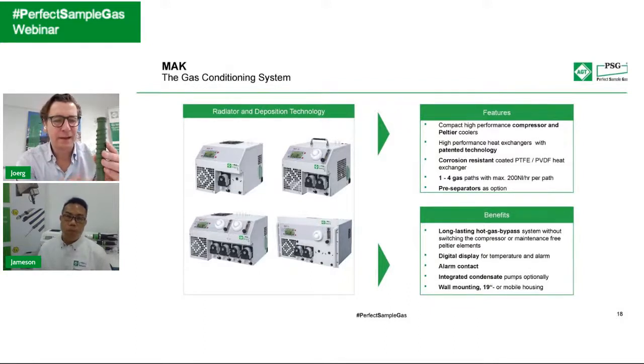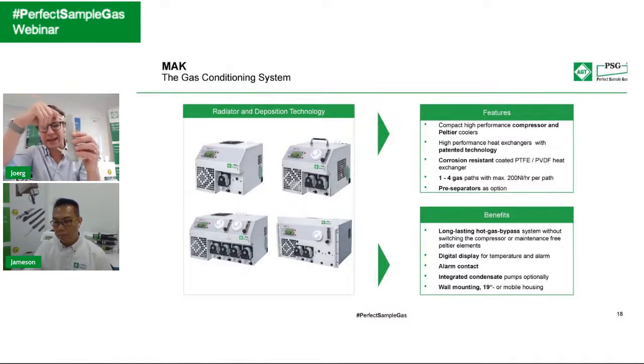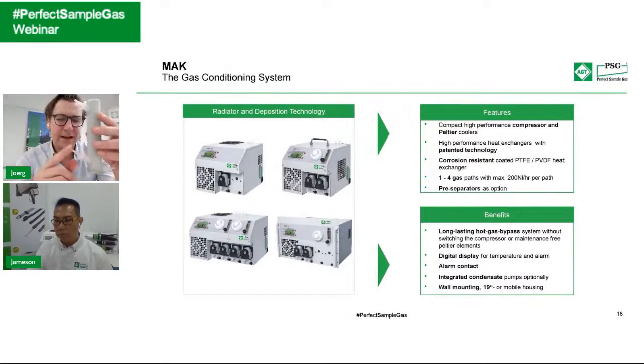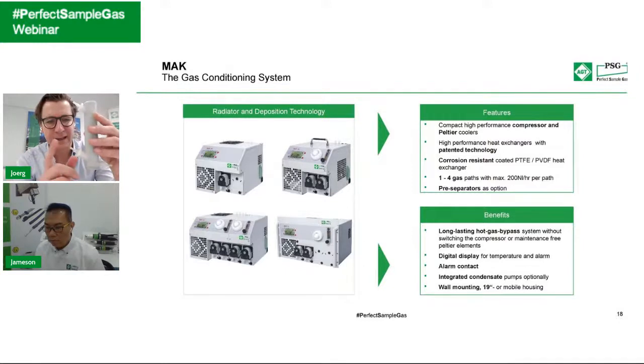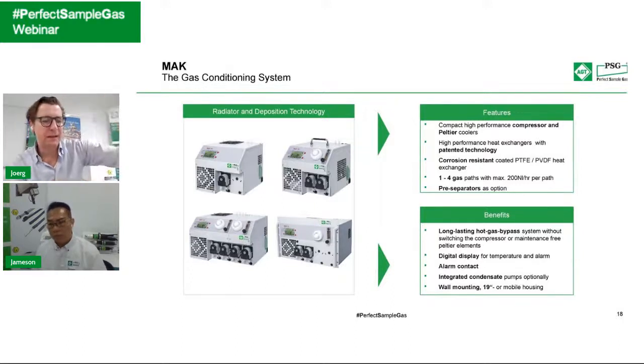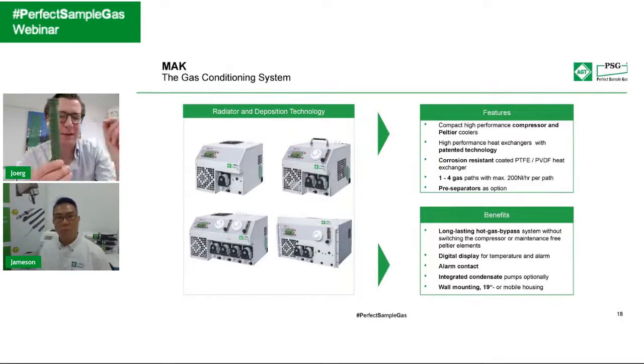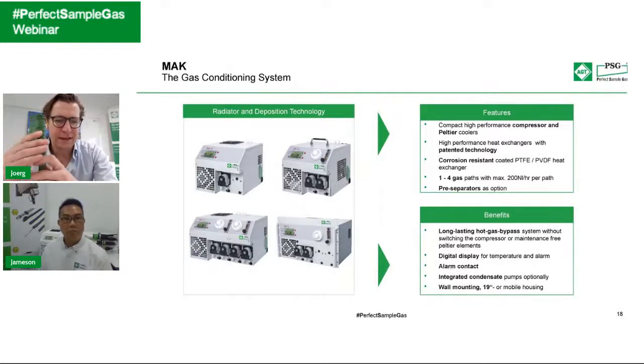And this PTFE coating also allows measuring very aggressive gases. And the big advantage of this technology is, or let me first of all describe how that really goes. The hot, wet gas comes in here and it is forced to go all the way down. Then we have the condensate, which comes out here, and the dry gas, which leaves the heat exchanger here.